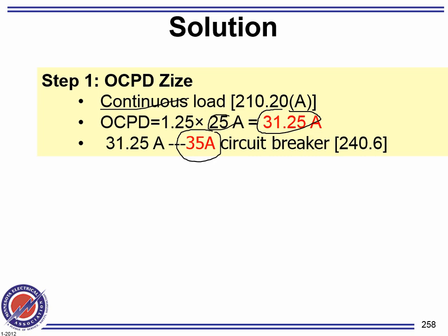There's no calculation for bundling and derating and temperature. You can't size the fuse based on bundling and derating. You can only size it based on continuous load and non-continuous load. If it's non-continuous load, match it to the equipment amp. So if your equipment is 90 amp, your breaker is 90 amp. If it's continuous load, your equipment is 90 amp, multiply by 1.25 and go to the next standard up.